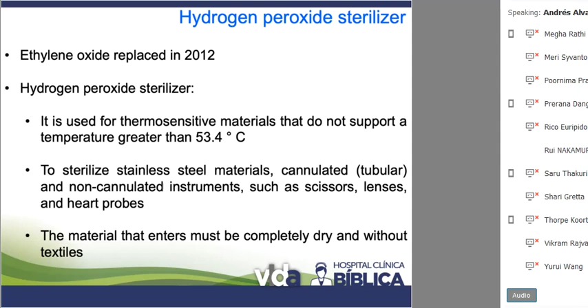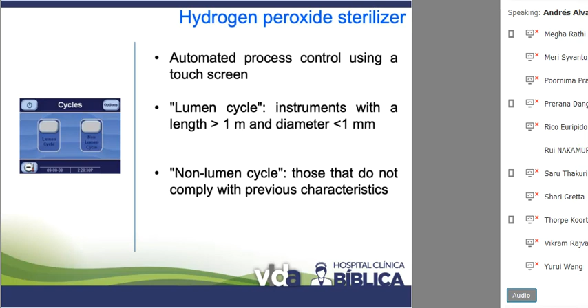One of the most important things here is that this hydrogen peroxide sterilization occurs in an automated process control using a touchscreen, which you can see here on the left side. And we have two types of cycle, the lumen cycle and the non-lumen cycle, considering instruments with a length greater than 1 meter and a diameter less than 1 millimeter in this case, and on the other one, those that do not comply with these previous characteristics.